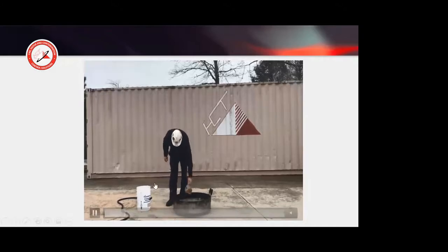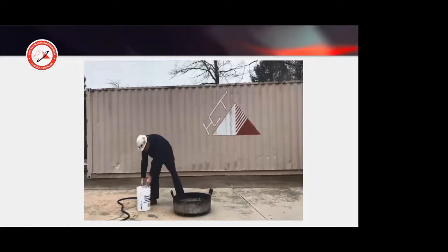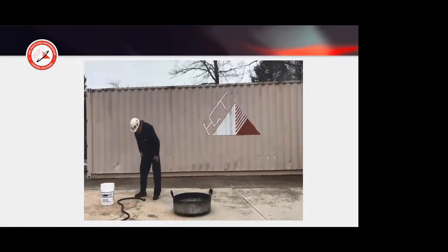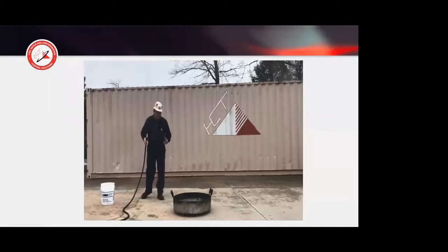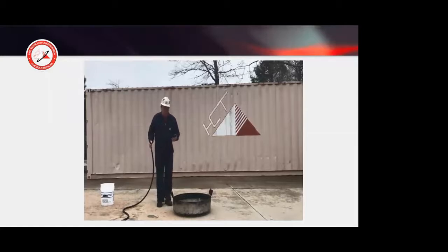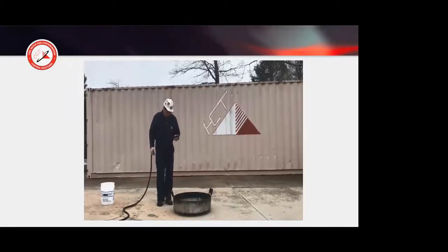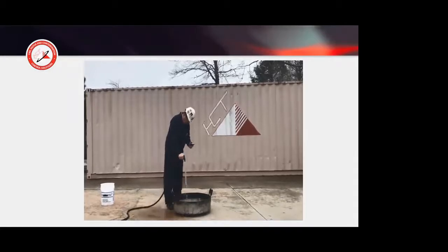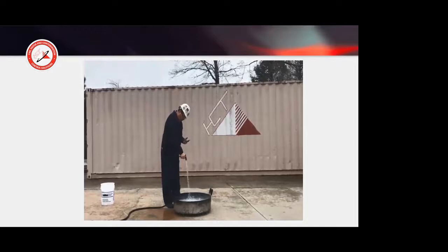First, the fuel. So we put in a gallon of fuel. Now we're mixing in a pint of the agent. If we were doing this metric, we would be putting in 4 liters of fuel and 500 milliliters of agent. So that's that 1:8 ratio. Now we're taking a calibrated nozzle. So if we're doing this in US units, this is a 5-gallon per minute calibrated nozzle, and we're going to apply for 1 minute. If we're doing the metric system, this is a 20-liter per minute nozzle, and we're going to do 1 minute.